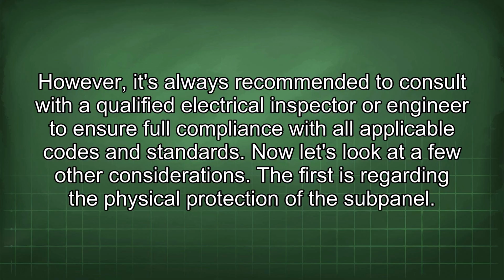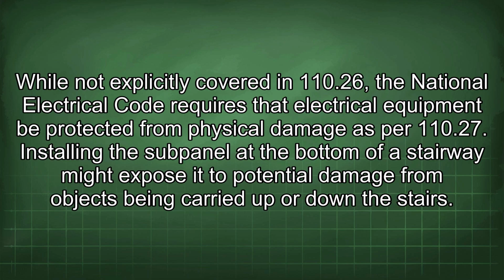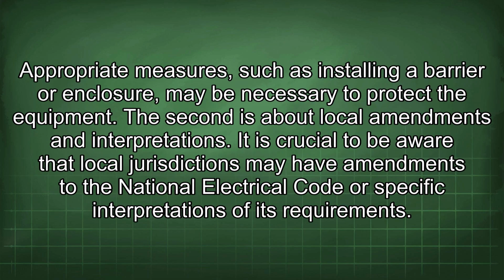applicable codes and standards. Now let's look at a few other considerations. The first is regarding the physical protection of the subpanel. While not explicitly covered in 110.26, the National Electrical Code requires that electrical equipment be protected from physical damage as per 110.27. Installing the subpanel at the bottom of a stairway might expose it to potential damage from objects being carried up or down the stairs. Appropriate measures, such as installing a barrier or enclosure, may be necessary to protect the equipment.